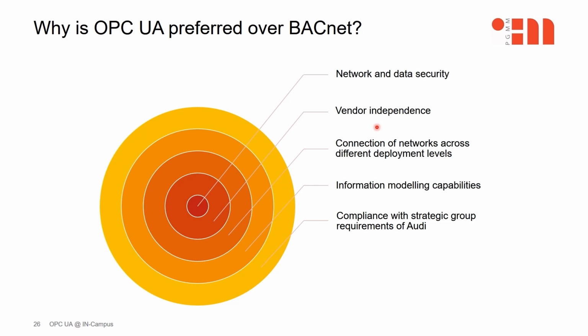Since OPCUA is an open standard that is not dominated by one manufacturer or manufacturer group, it offers customers the possibility to remain manufacturer independent. In addition, OPCUA offers the ability to connect multi-vendor networks across different deployment levels from the control level to the enterprise level. Furthermore, OPCUA makes it possible to define information models independently. That means without the involvement of the OPC Foundation, to release them for campus-wide use and to dynamically adapt them to expanded needs in the future. This special feature guarantees Audi high flexibility and productivity without loss of conformity to the standard.